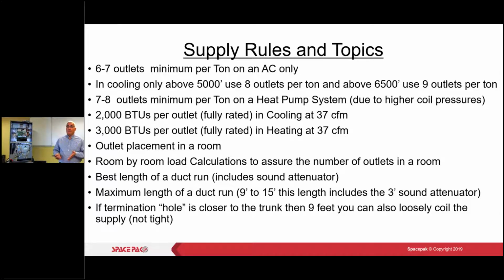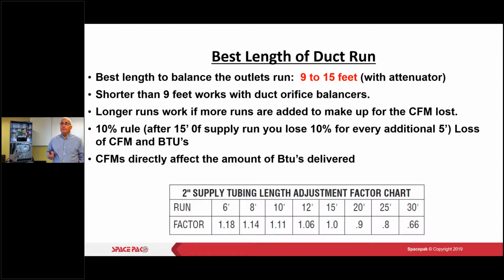When we do our run, the maximum length of the duct run is 9 feet to 15, and this includes a 3-foot sound attenuator, which you do need at the end. Otherwise, it's going to sound very, very loud. So here's what we want to do. We want to stay within that 9 to 15 feet. Shorter runs at 9 feet are better. We could use those duct balancing orifices, but we try to stay away from that because that could make some noise. So if it's going to be a really short run, maybe just coil it up and come in, because those balancing orifices can make some noise.